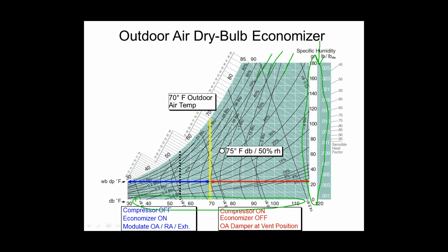So if I was to set your economizer for 55 degrees, that's this black dotted line over here, right? Anything to the left of that line would have been an economizer day, and anything to the right of that line would have been a compressor day. Now I'm going to move that line over to where the yellow one is at 70 degrees, right? So everything in between there, those 15 degrees of outdoor temperature on the bin chart, are now available to me for an economizer mode, right? So a dry bulb is pretty straightforward. I got a 70 degree set point. I got a temperature sensor. If it's below 70, economize. If it's above 70, compressors. All right. We'll talk about integrated economizers here in a second too. For right now, we'll just hold off on that.